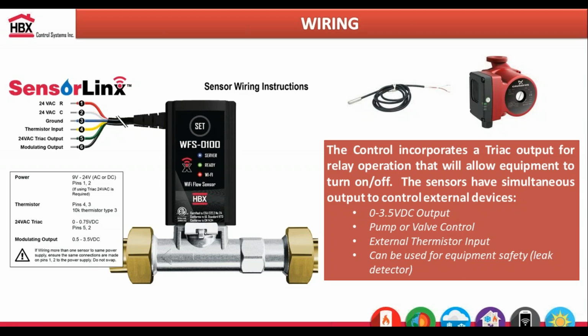We also have an option for relay operation. If you wanted to control a pump or a valve based off temperature, pressure, or flow, we can activate that relay to operate it. Say you had a leak in your system and your flow were to drop, we can close that pump or valve. Or if your boiler is putting out too much heat, or has too much pressure, you may want to open a pump to relieve that pressure. So you can use these sensors for temperature, flow, and pressure calculation, but also as an equipment safety device, which makes it real beneficial.